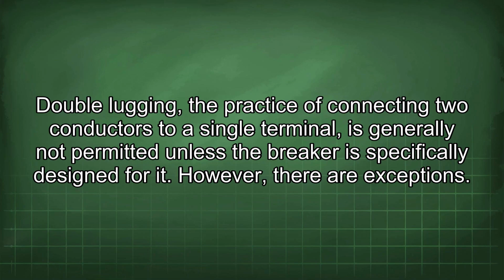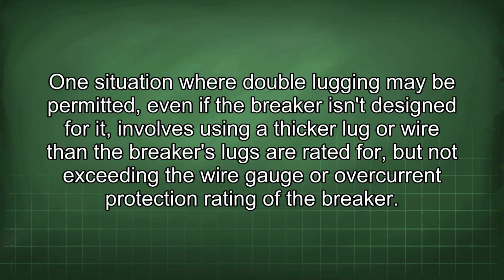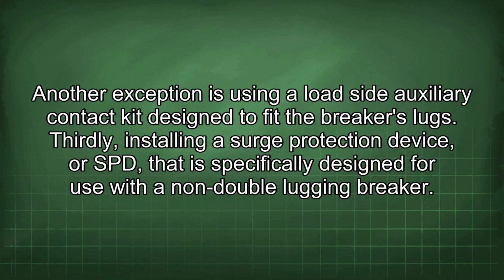Double lugging, the practice of connecting two conductors to a single terminal, is generally not permitted unless the breaker is specifically designed for it. However, there are exceptions. One situation where double lugging may be permitted, even if the breaker isn't designed for it, involves using a thicker lug or wire than the breaker's lugs are rated for, but not exceeding the wire gauge or overcurrent protection rating of the breaker. Another exception is using a load side auxiliary contact kit designed to fit the breaker's lugs.